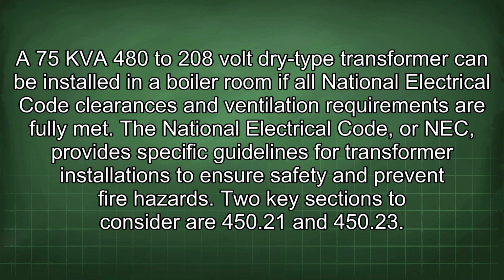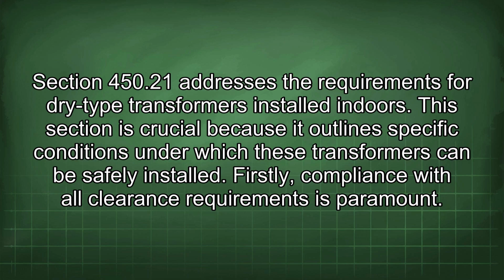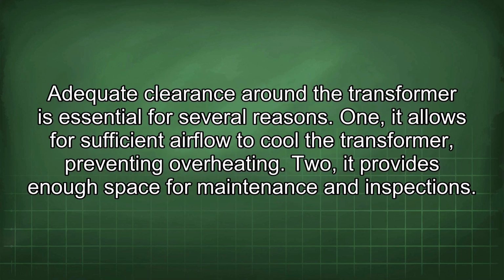450.21 and 450.23. Section 450.21 addresses the requirements for dry-type transformers installed indoors. This section is crucial because it outlines specific conditions under which these transformers can be safely installed. Firstly, compliance with all clearance requirements is paramount. Adequate clearance around the transformer is essential for several reasons.